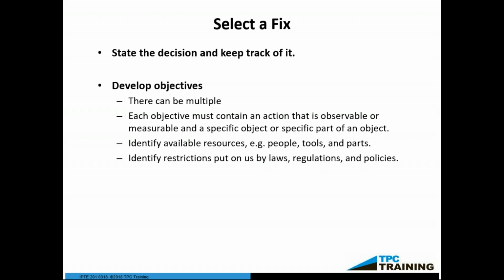You ever think at the end of a shift nothing happened? Why not put in there something like, the machine ran great, I read all my pressure gauges and all my pressures were good, and I noted my pressures: gauge number 1 was 60 psi, gauge number 2 was 5 psi. Because when something's not working right and all of a sudden the first gauge reads 5 psi when it used to be 60, and the second gauge reads 60 when it should be 5, what do you think happened?